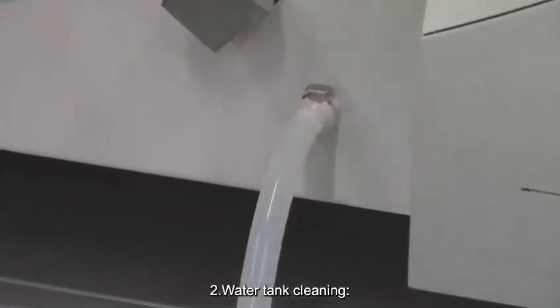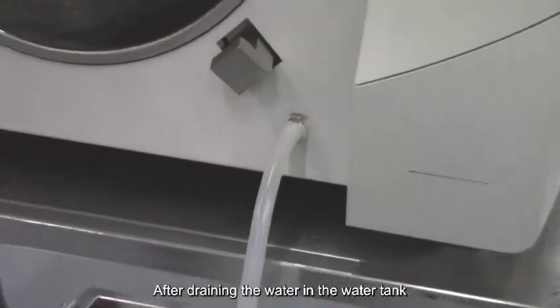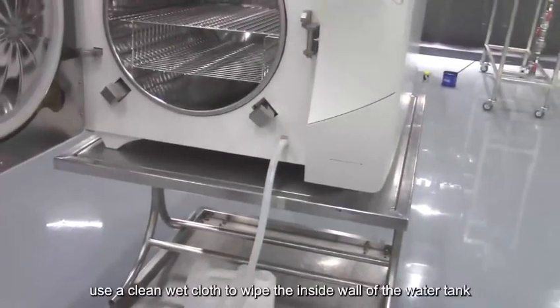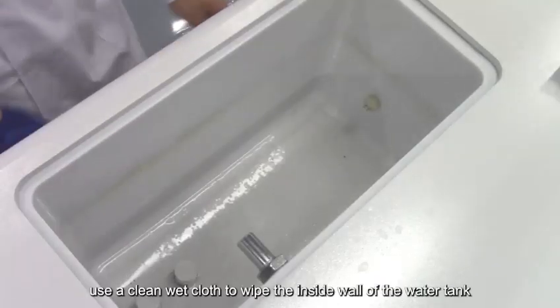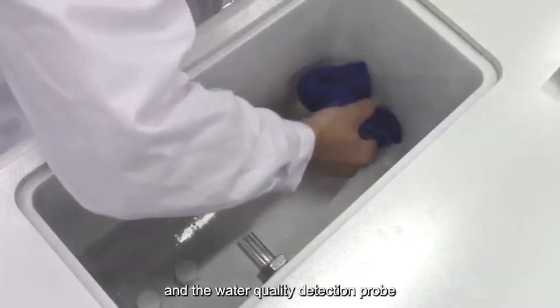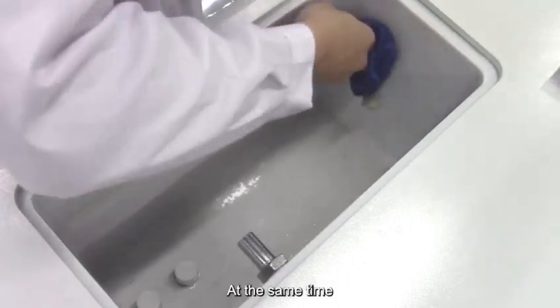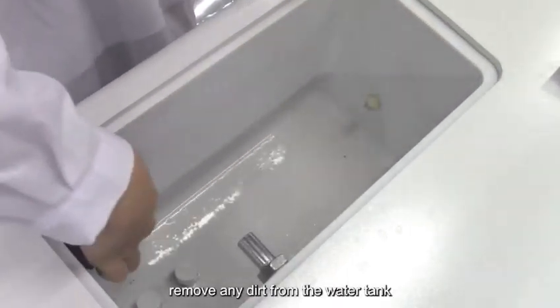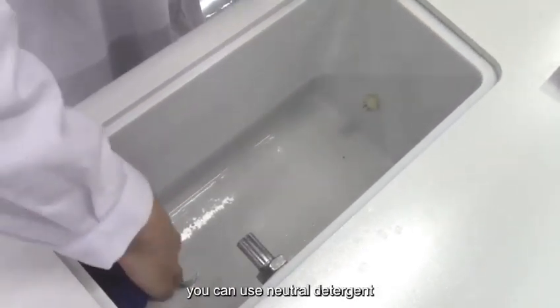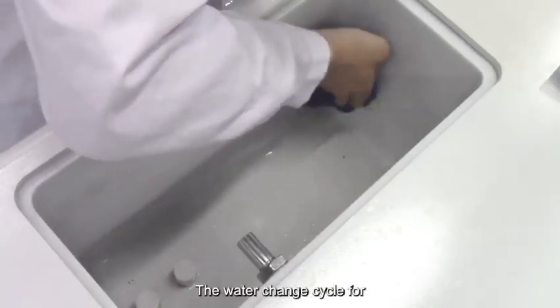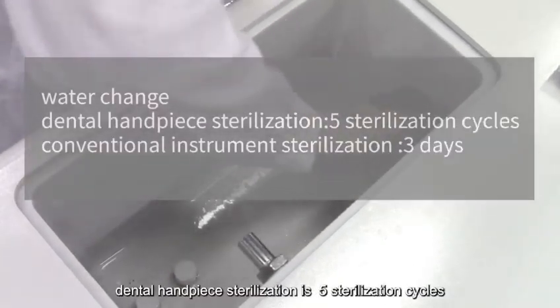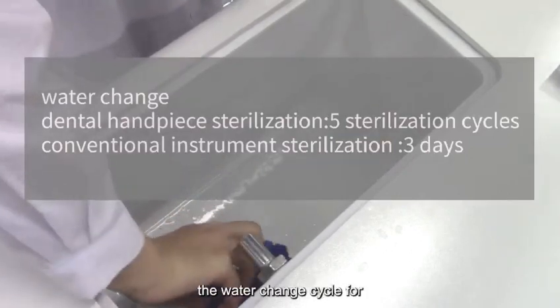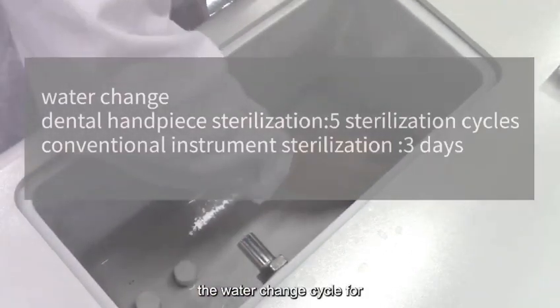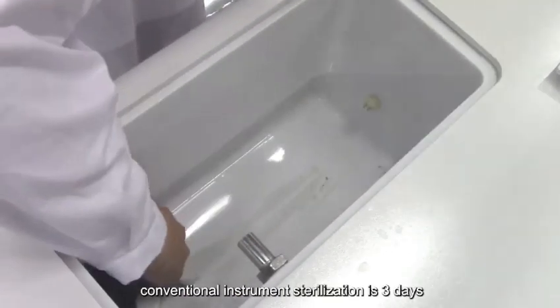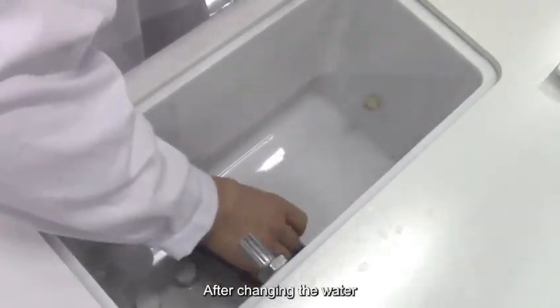2. Water tank cleaning. After draining the water in the water tank, use a clean wet cloth to wipe the inside wall of the water tank and the water quality detection probe. At the same time, remove any dirt from the water tank. If you cannot completely wipe it clean, you can use neutral detergent. The water change cycle for dental handpiece sterilization is 5 sterilization cycles. The water change cycle for conventional instrument sterilization is 3 days. After changing the water, the water tank needs to be cleaned.